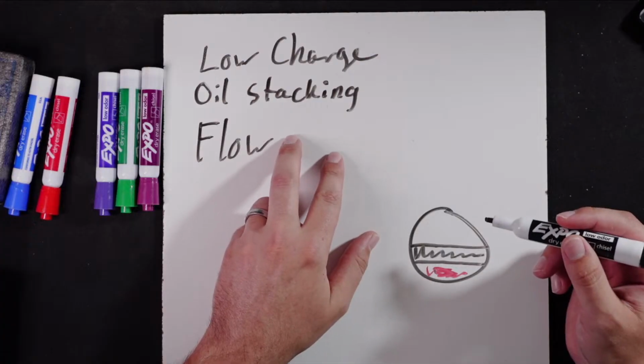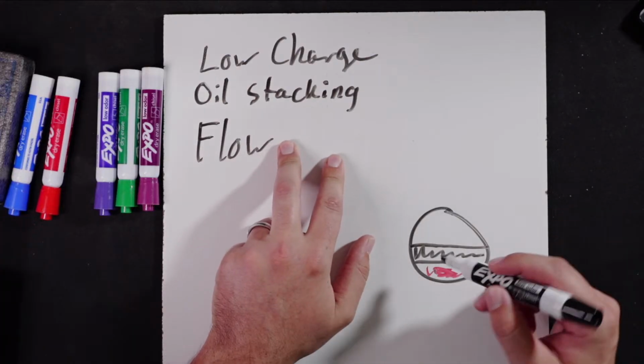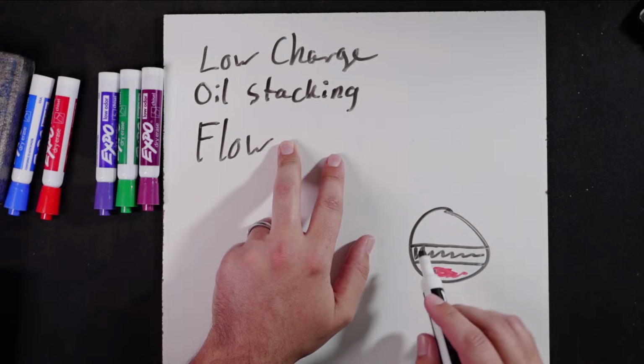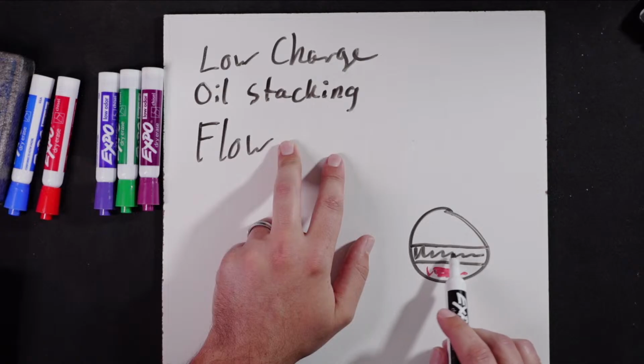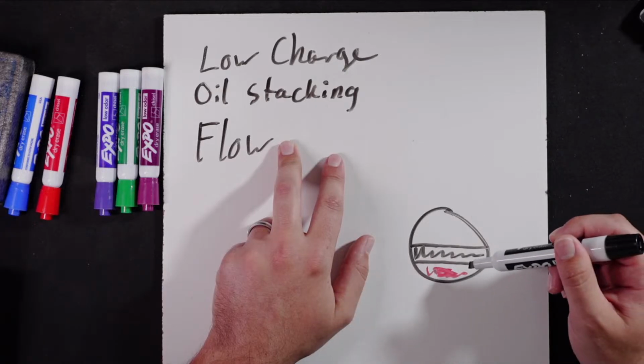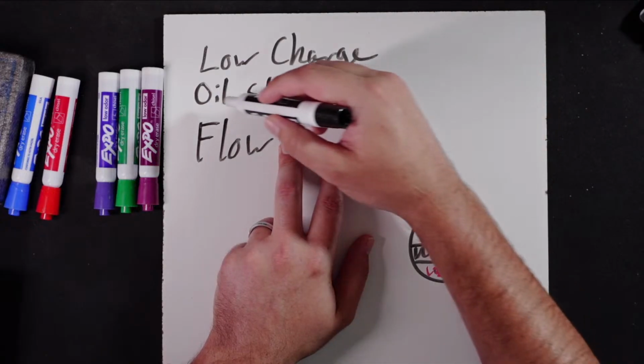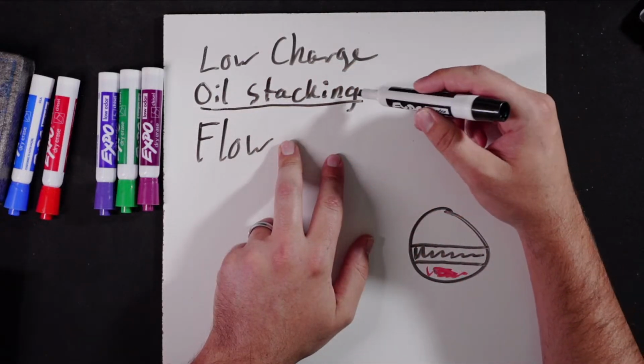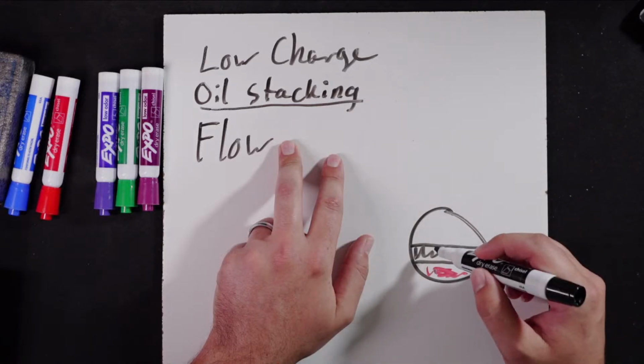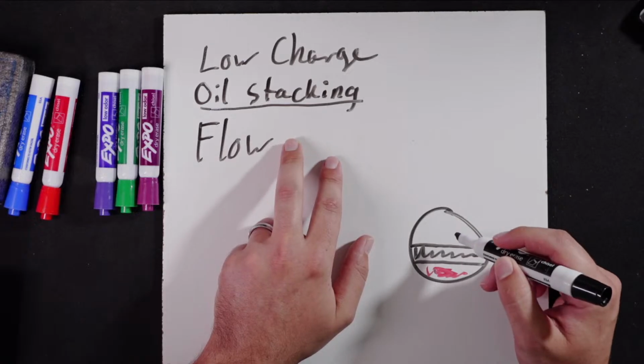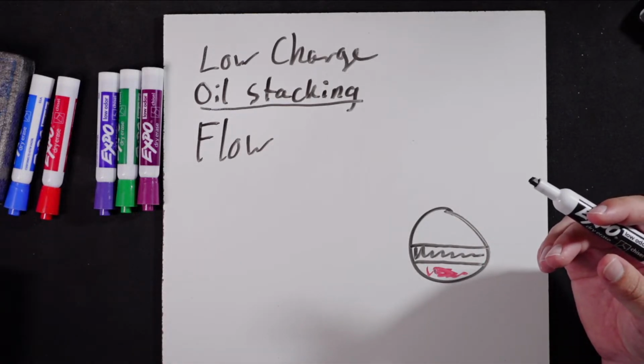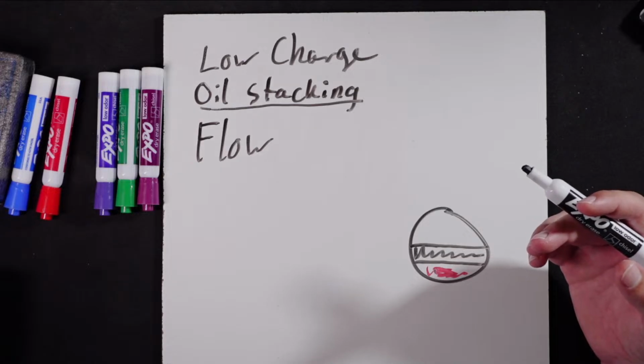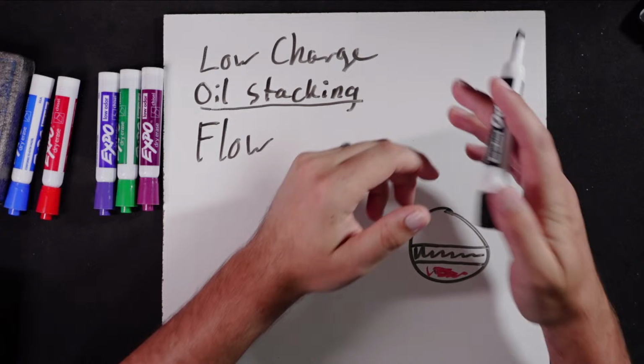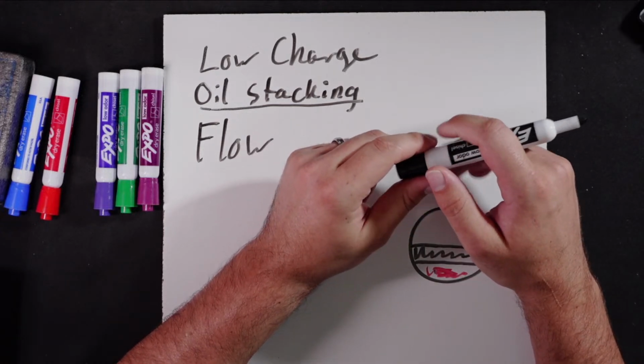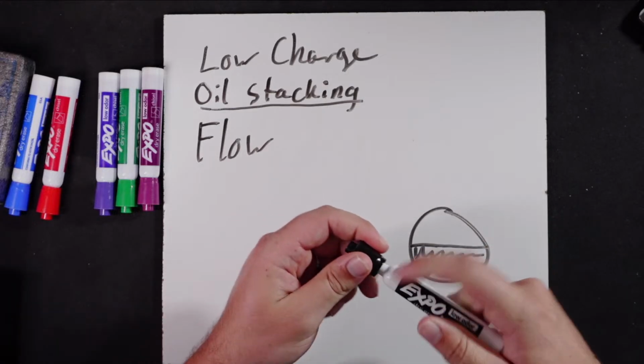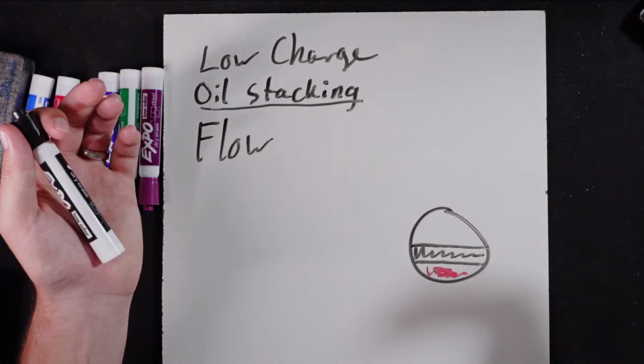And this might be what helps me determine between oil stacking or flow. If the liquid level is still up in this zone, even though I've got suction limiting, I'm probably going to start looking at the oil stacking far more heavily. Because at that point, this oil is getting stuck in the evaporator and it's causing a heat exchange problem, which is causing my suction limiting. Now, you said it's both circuits, so the likelihood that that was identical on both circuits, I would say, is less likely.